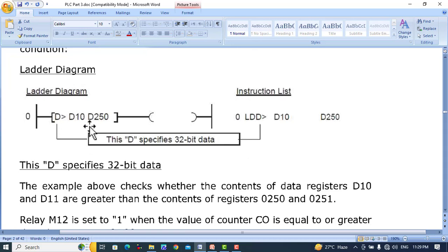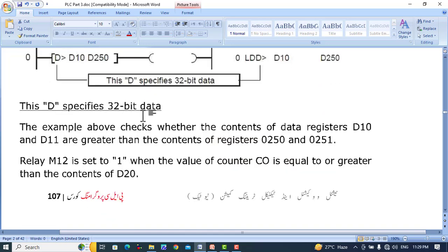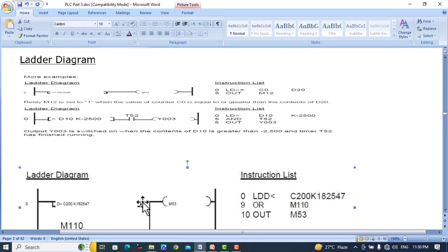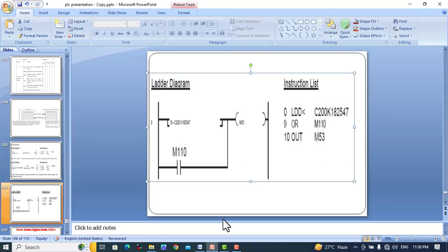Here is an example of a 32-bit comparison: D> D10 D250 will compare the values of D10 and D11 with the values of D250 and D251. If the value of the first two registers is greater than the second two, the output will be turned on — it takes consecutive registers automatically. Another example: D< C200 K182547 will compare the 32-bit counter C200 value with the numerical value 182547. When the counter value is less than K182547, output relay M53 will be turned on.